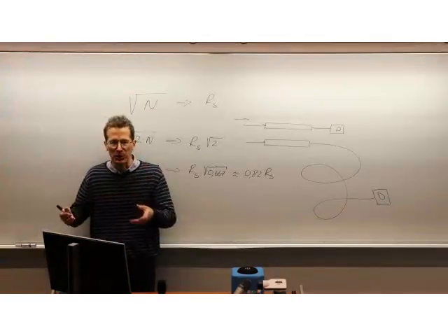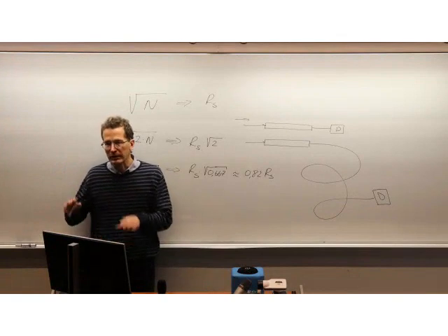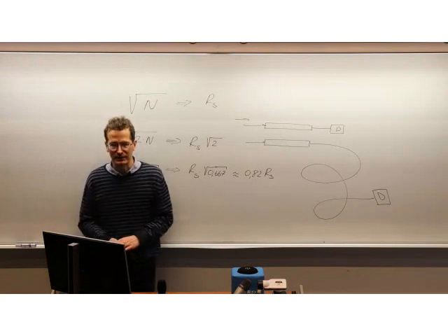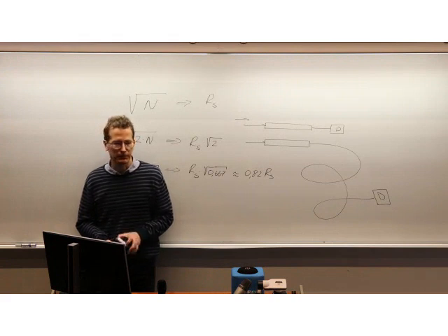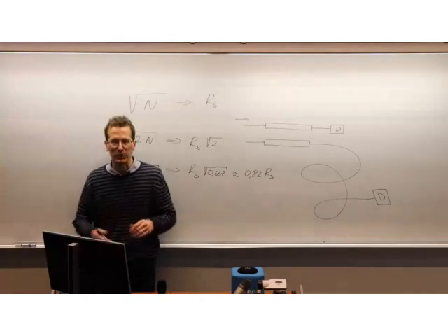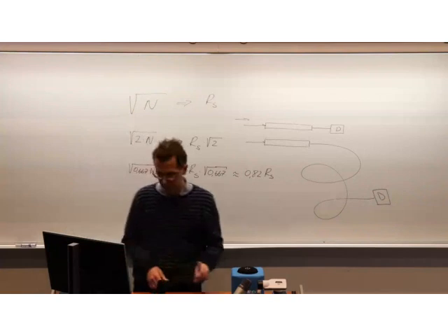And then again, it switches on and blows cold air. And if by chance it's blowing the cold air on the column, then this is quite an impact, and this can be visible in the chromatogram, those differences. So even if not using a column thermostat, then it's a good idea to at least isolate the column from direct wind blowing on it, from the air conditioner.